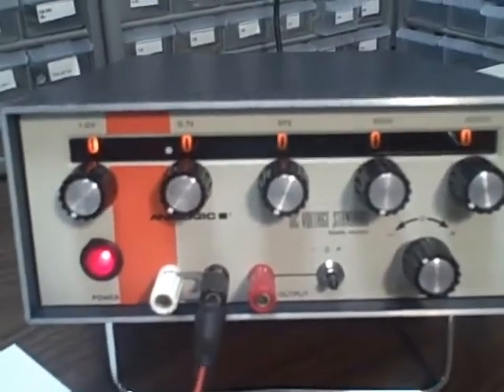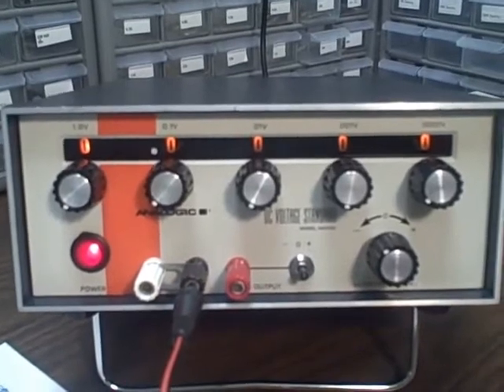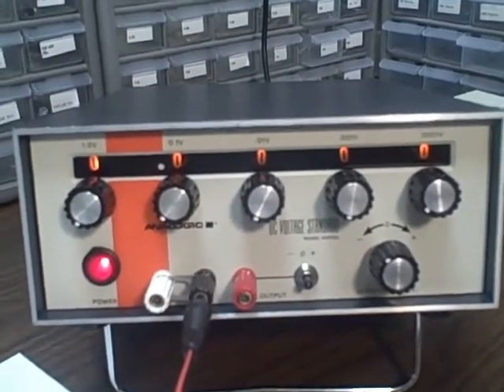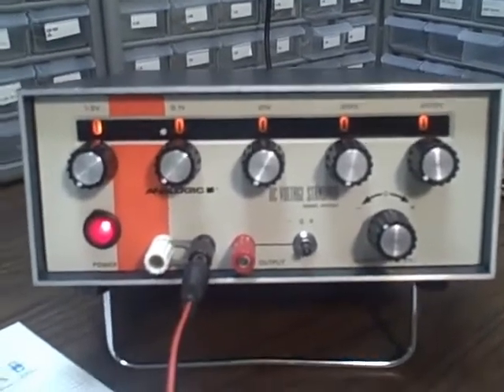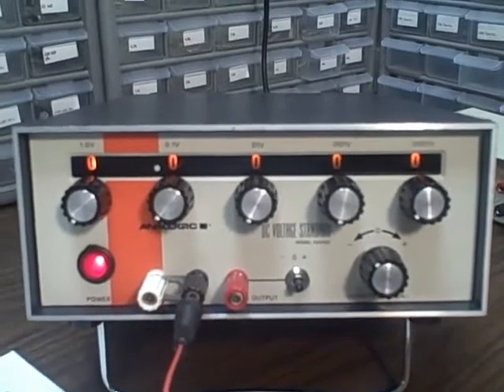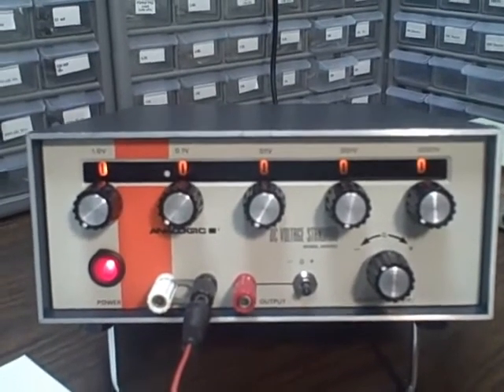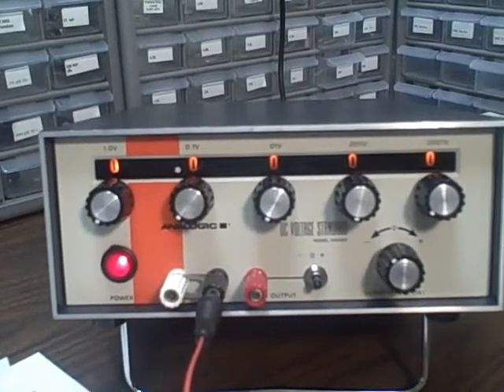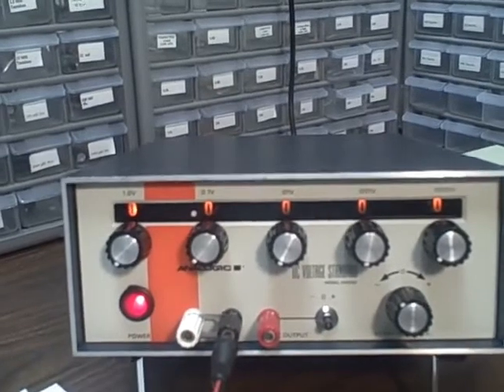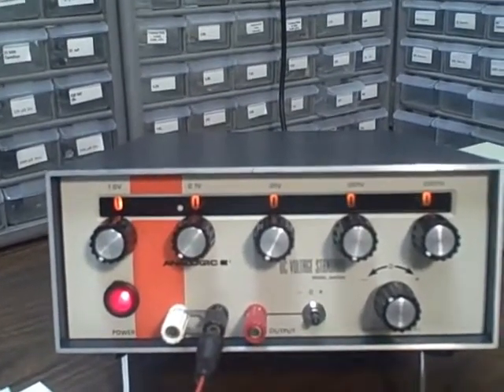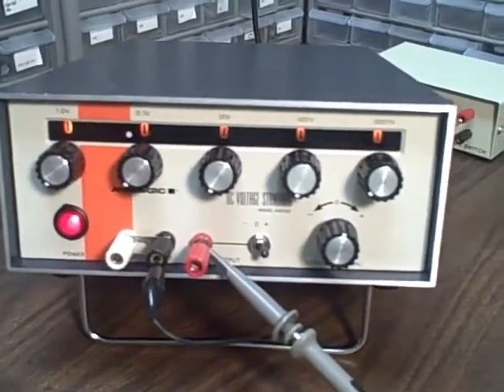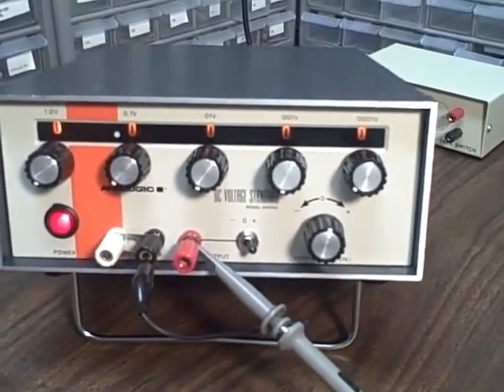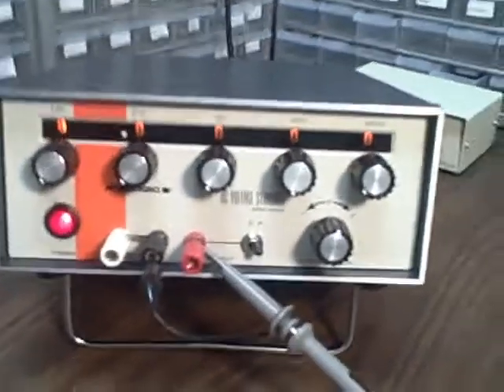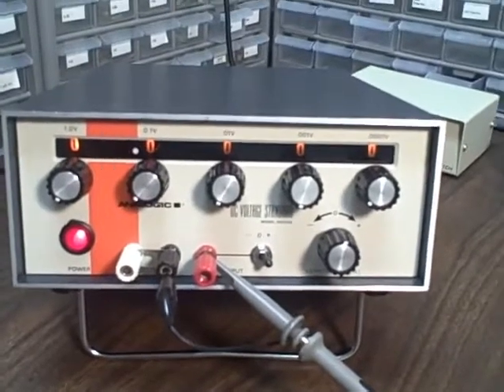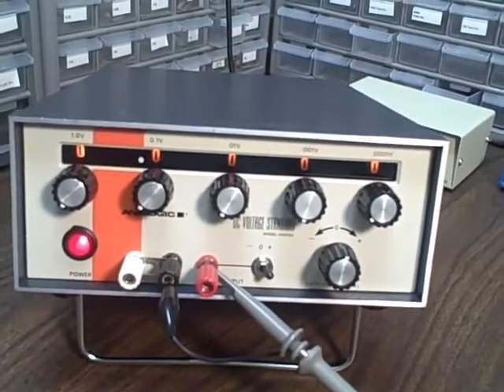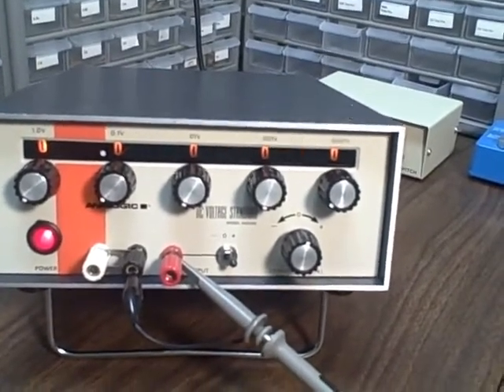Okay, what we're looking at tonight is an Analogic model AN3100 DC voltage standard. This DC voltage standard is portable. It heats up very quickly, in about 10 minutes, and provides precision DC voltages in 100 microvolt increments all the way up to about 11.11 volts. It's portable and it works very well, with a very clean output, and it's wonderful for calibrating meters, for testing scopes, anywhere you'd need a standard voltage applied.